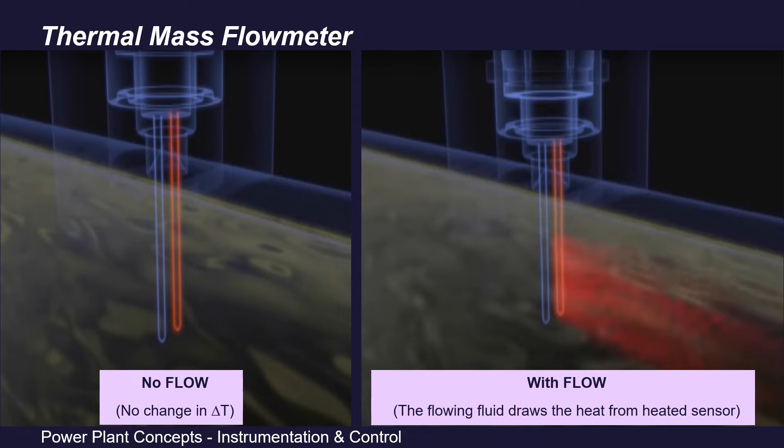But as soon as the fluid begins to flow in the pipeline, the flowing fluid draws the heat from the heated sensor. The corresponding cooling effect is immediately measured. And to maintain the same temperature difference of 15 degrees, the second sensor is heated more by providing more electrical current. This heating current required to maintain the temperature difference is proportional to the cooling effect.